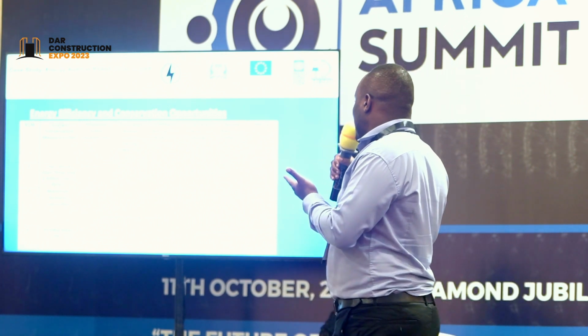At the same time, we also found that at night they are using more of the cooling system, but there are no occupants, because most of the tenants are offices and office time is normally 6 or 7. So they are using more energy while there are no occupants. These were the recommendations we found after analyzing and assessing, and we found that we can save more than 40 or 50 million within a short period just by optimizing chiller usage.